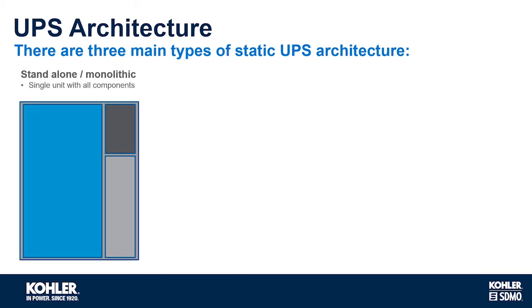So we put UPSs into three main types of architecture. On the left, we have a standalone, sometimes called monolithic, type of UPS. This is a single UPS, and this will have just the one of each component: one rectifier, one bypass, one inverter, and it's typically sized for the load you want. Okay, so if you wanted a 500 kilowatt load, you'd put a 500 kilowatt single UPS in.